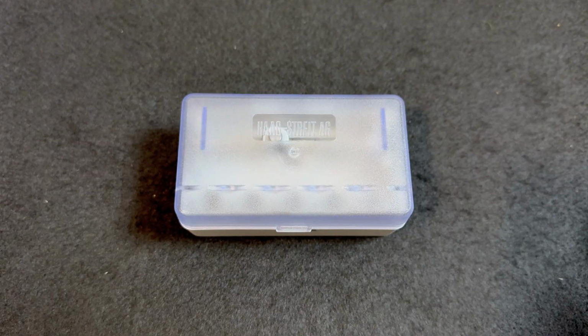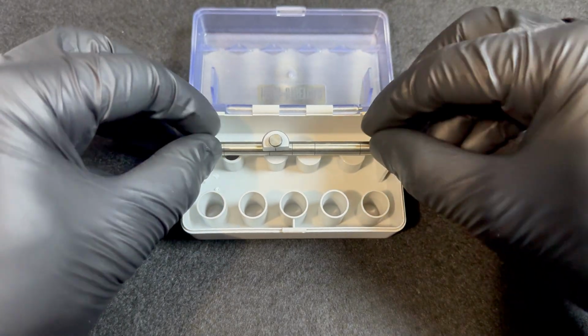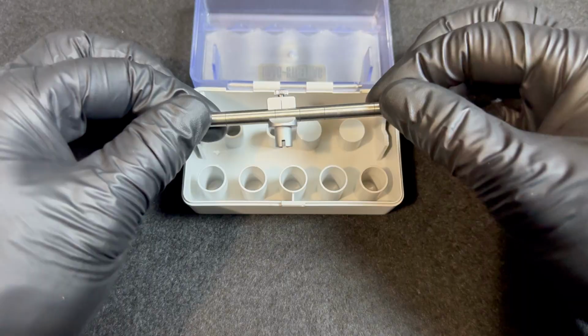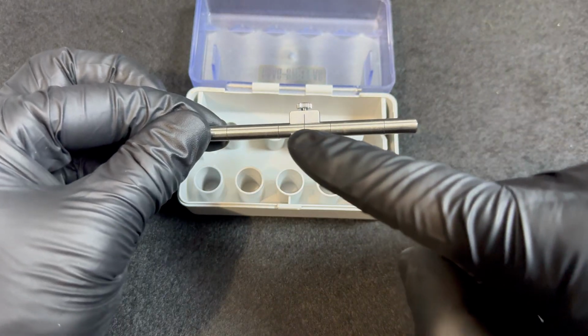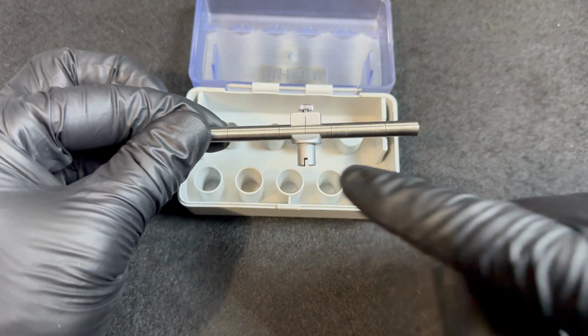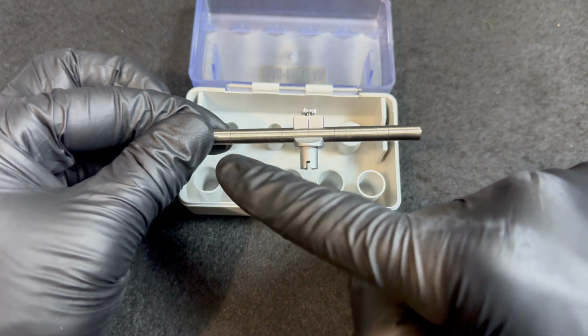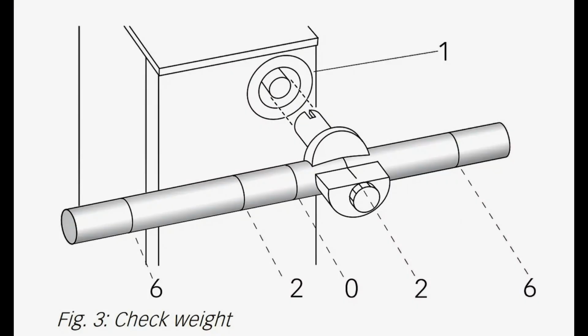To perform this check, you'll need the control weight, also called a calibration or check bar. The control weight has 5 engraved circles. The center mark is for 0, the 2 inner marks are for 2, and the 2 outer marks are for 6. Here is the diagram inside the manufacturer's user manual. We'll start by testing the 0 setting, which is performed without the test bar.